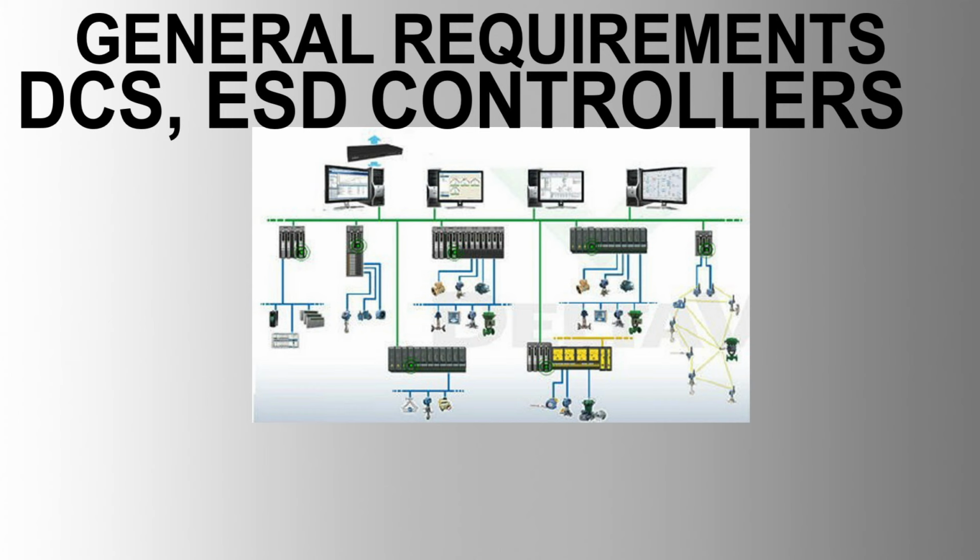4. Operator workstations. Specifications. High-resolution color graphic screen of at least 21-inch, capable of displaying mixed alphanumeric and graphic data. Sealed membrane keyboard with alarm annunciator LEDs. Trackball or mouse equipped with push buttons. Input-output mass storage units, floppy disk, DVD, CD-ROM drive. Ethernet communication interface module. Workstations should support object-oriented distributed computing with client-server architecture, OPC client-server connectivity, and Explorer tree navigation with multi-window support.